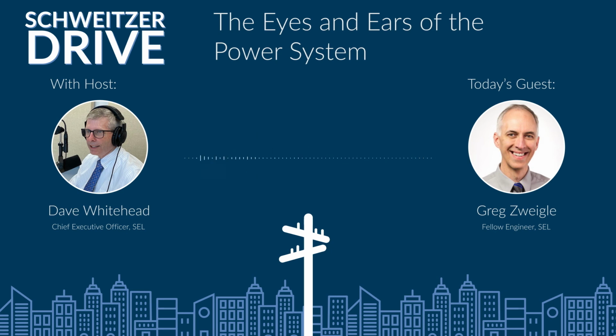Yeah, that's a great question. Like we talked earlier, synchrophasors are based on that phasor approximation. So we say the power system signals have a wave-like shape, and that's true. And like we mentioned, that's in large part because of those spinning generators that are rotating at that fixed frequency. But this phasor approximation, it's an approximation. The actual shape is a bit more complex, and especially with renewables and inverter coupled devices, the power system is changing. So synchrophasors, while they are a major advance for our industry, they're definitely limited by the fundamental assumption that the power system waveforms are shaped like a sinusoid.